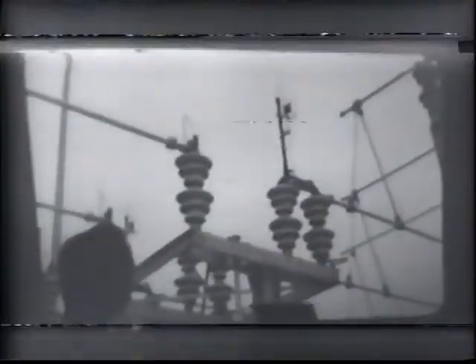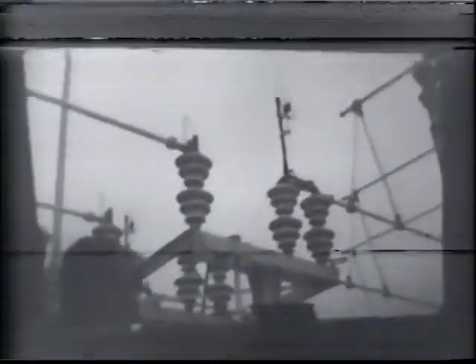And this is another example of sub 27. Line trap here, shielding masts here. In this case, we don't use a shielding wire. We just have the tall poles sufficient to provide a 45-degree cone of protection over all the equipment.